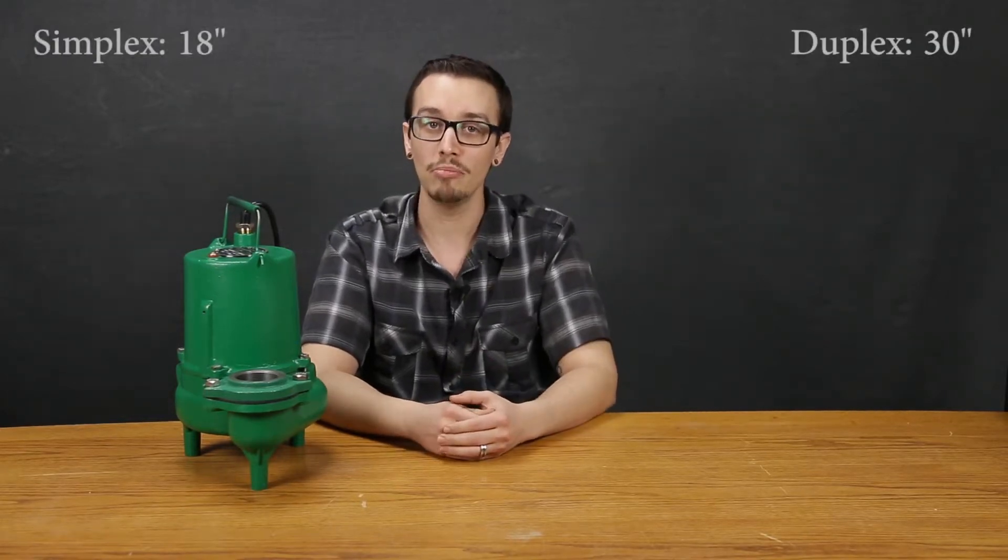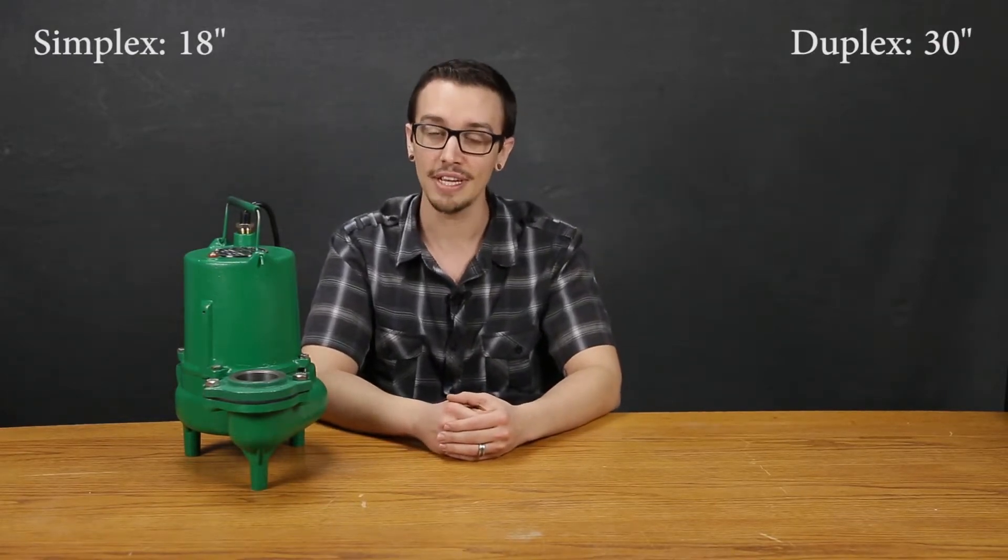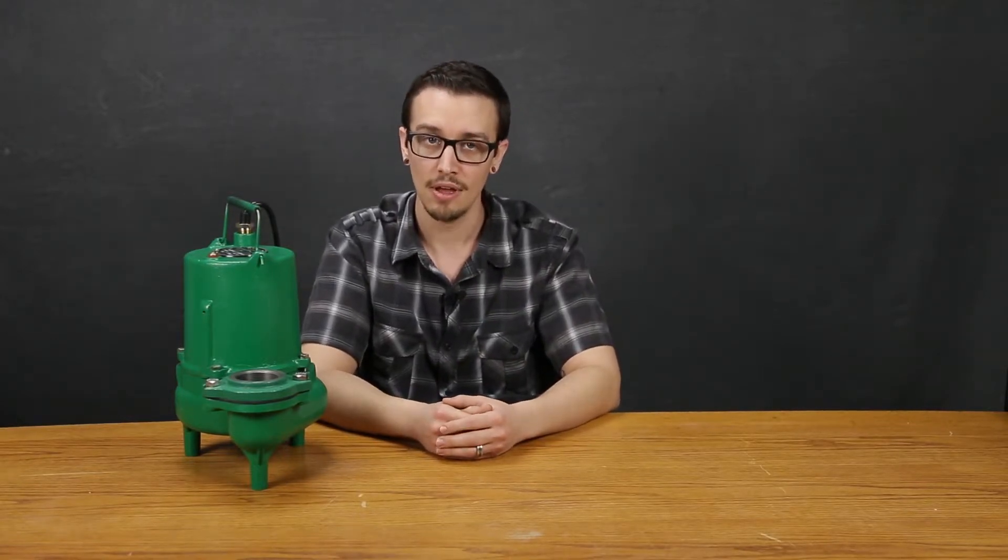The minimal sump diameter for these pumps in a simplex configuration is 18 inches and 30 inches for a duplex configuration. By maintaining this minimal diameter, we're ensuring that the equipment has enough room for proper operation and to help eliminate cord entanglement.